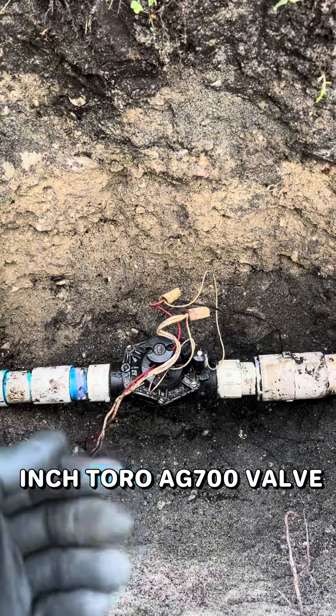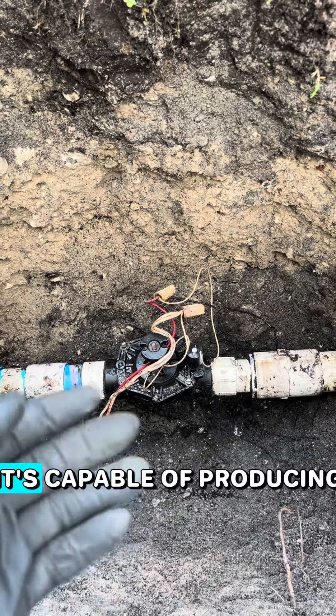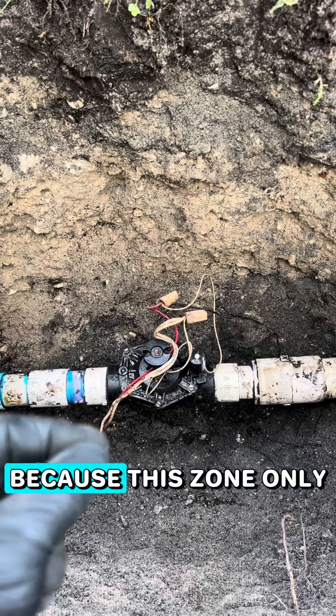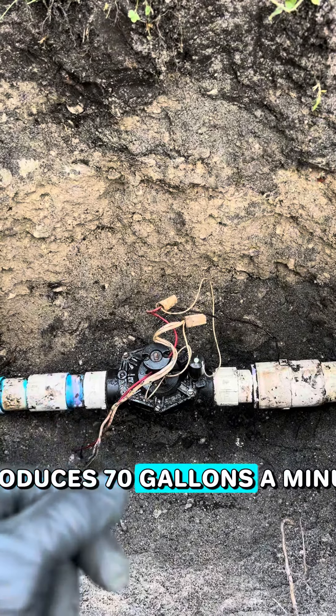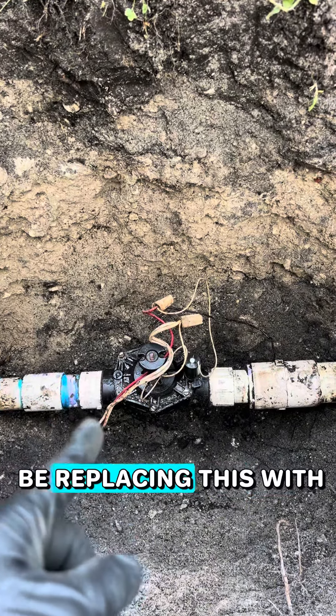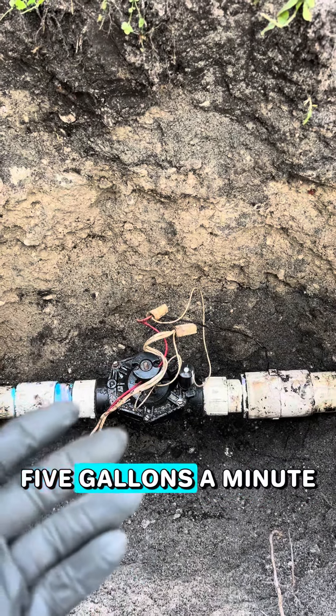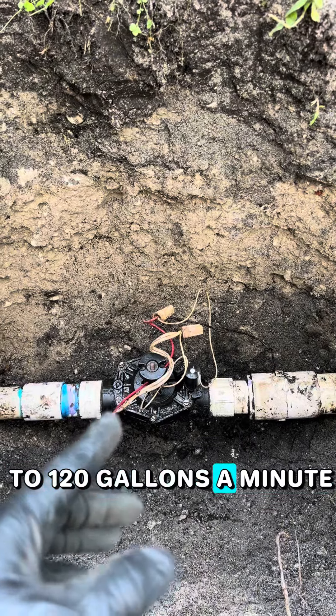This is a 2-inch Toro AG700 valve. It's capable of producing 180 gallons a minute, which we don't need because this zone only produces 70 gallons a minute. The valve I'll be replacing this with will be an Irritrol 200B valve, capable of 5 gallons a minute to 120 gallons a minute.